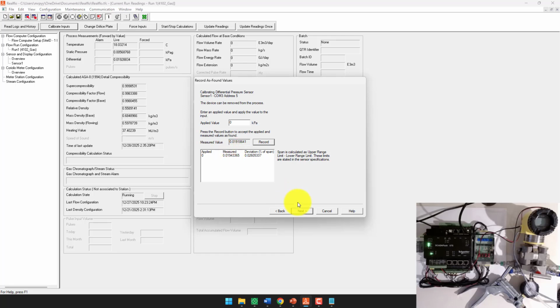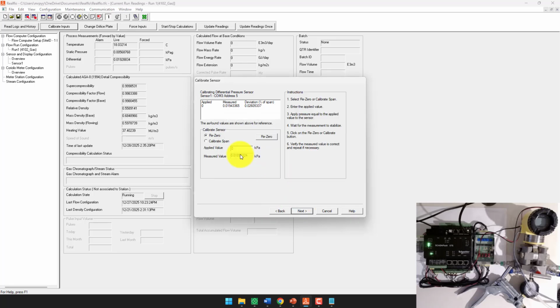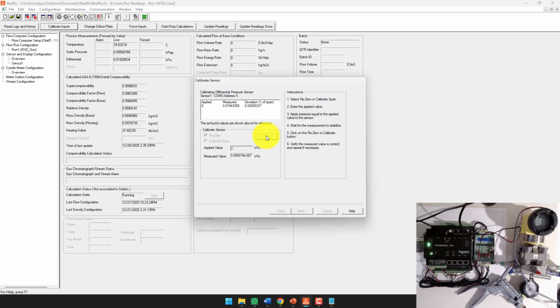So it's a little bit off, but barely. We will calibrate this device. Hit next. We'll do the re-zero first. And if you had an accurate pump, you could calibrate the entire span. I don't have an accurate pump, so I won't be doing that. We're just re-zeroing it for this video. Hit next.